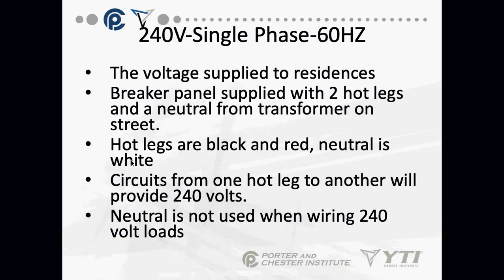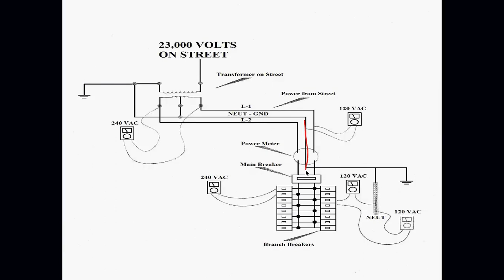So again, this is our circuit. L1 might be on one side, L2 on the other, with neutral in the center. Neutral is weird because it's not only the center point of the transformer, but it's also grounded in numerous different places, or it should be.